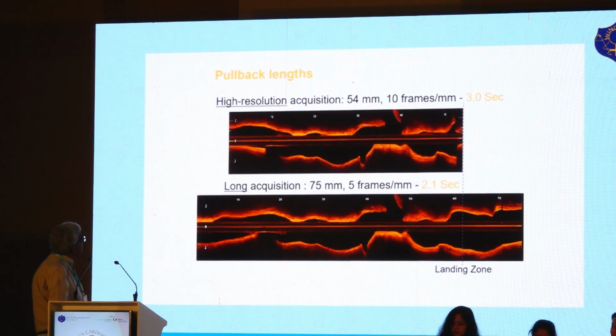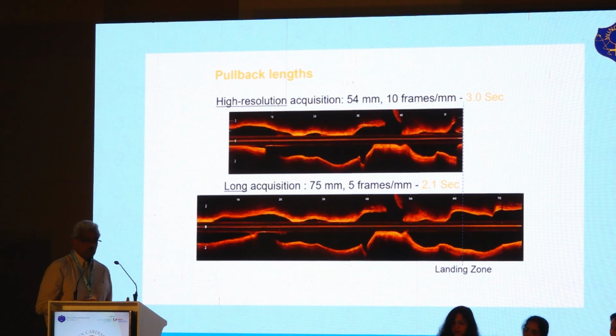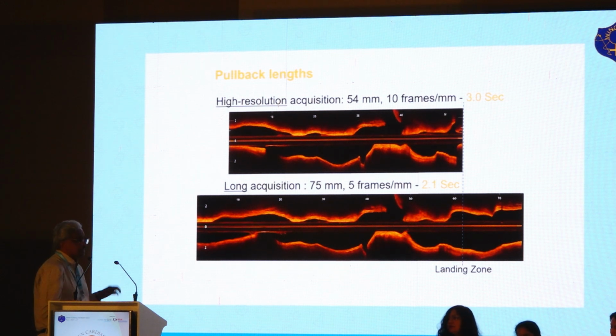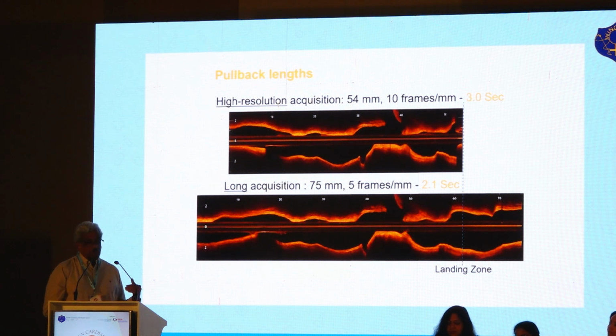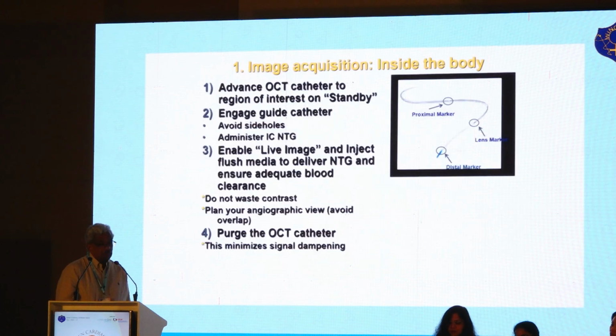Now, when you take a pullback length, you need to know what you are looking for. Do you want high resolution or do you want length? This determines whether you take a 54 millimeter or a 75 millimeter, and you have to adjust your frames per second accordingly. For example, if you want a high resolution image, we would use a 54 millimeter pullback, 10 frames per millimeter, at 3 seconds. While if you have a long acquisition, when you want a bigger length to the balloon, you will take 75 millimeters, 5 frames per millimeter, with a 2.1 second pullback. So this is important before you decide what you want to do.